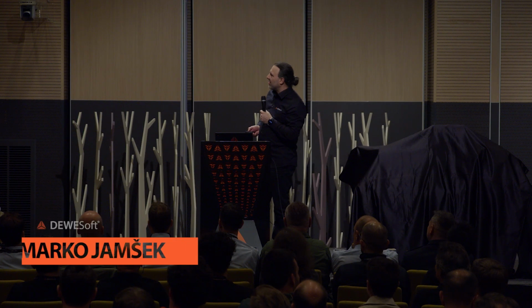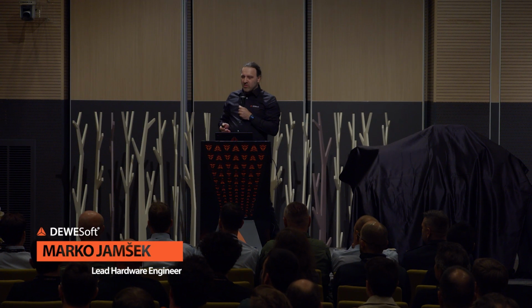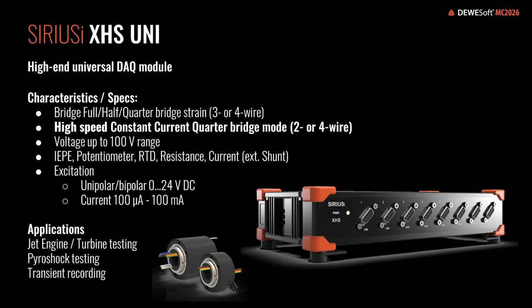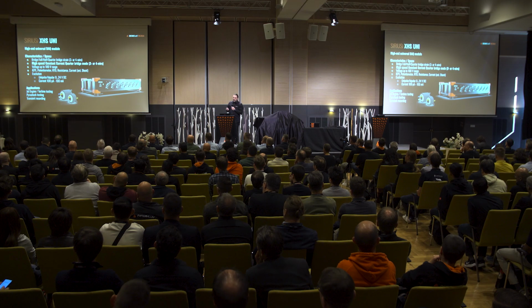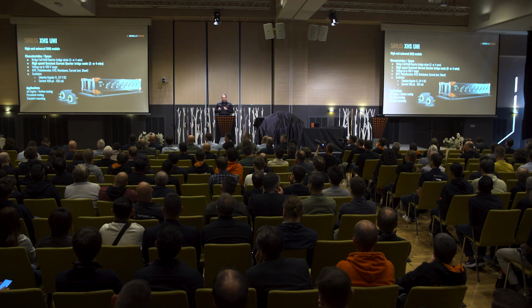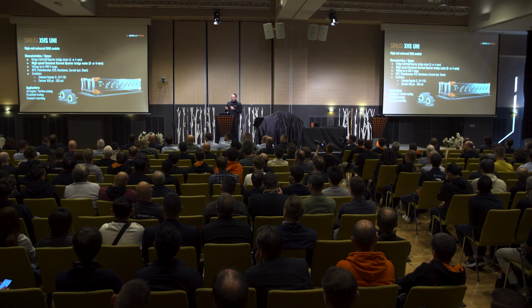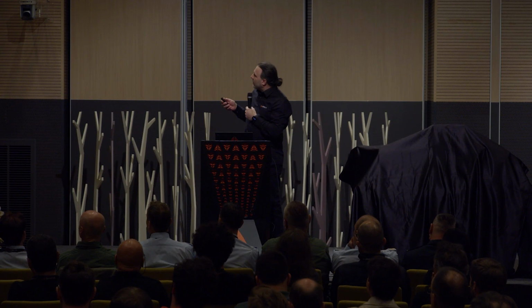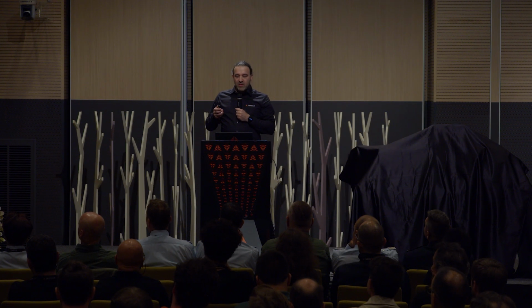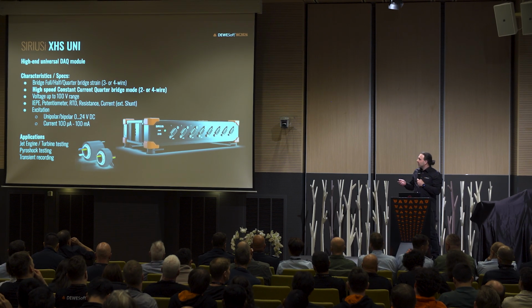So let's start with XHS Uni amplifier. We already introduced this one on previous measurement conference, but we made some upgrades. Now it can measure still with high speed, high precision, and low noise down to microvolts. But what we added was new feature for constant current excitation. This is where user can select high speed, constant current quarter bridge. And with this setting, it's possible to measure high-speed transients, for example, with slip rings in jet engine testing.